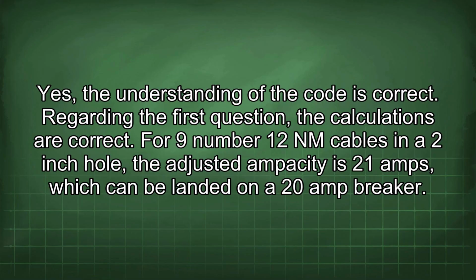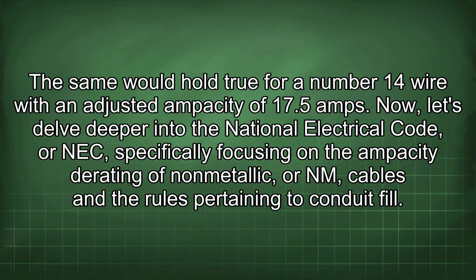Yes, the understanding of the code is correct. Regarding the first question, the calculations are correct. For 9 number 12 NM cables in a 2-inch hole, the adjusted ampacity is 21 amps, which can be landed on a 20 amp breaker. The same would hold true for a number 14 wire with an adjusted ampacity of 17.5 amps.